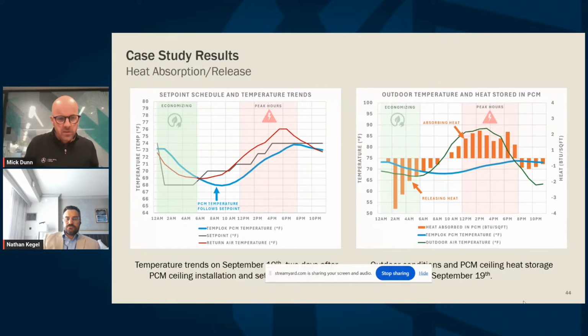Before people are coming in to work for the day, we're raising the temperature back up to the 70-degree comfort point. And then once we hit mid to late morning, we're slowly beginning to incrementally increase the set point from 71, up to about 72.5 degrees mid-afternoon, all the way up to 74 degrees late afternoon. And so the idea is we're not turning off our HVAC, but beginning to slowly set back HVAC earlier in the day as the building begins to empty. Typically, if the building were setting back later at night, it might be doing that at 5, 6 or 7 o'clock when the building is empty, just shutting off to say 80 degrees. In this case, it's a slow release before that final setback takes place.